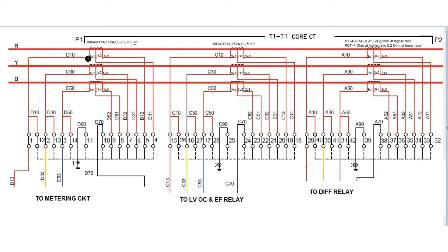There exist two ratios: 600/1 and 400/1. There are three terminals on the CT secondary side — S1, S2, and S3. For the metering core there exist 1S1, 1S2, and 1S3 for red, yellow, and blue phase respectively. Similarly, for the protection core — the overcurrent core — there exist 3S1, 3S2, and 3S3 respectively.